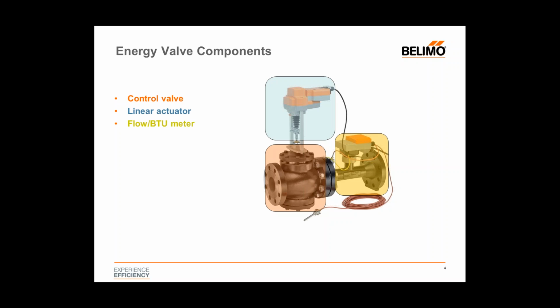The flow meter is now a BTU meter because we add 2 temperature sensors on this assembly. And that's how we understand the delta T and how we conduct our delta T management. One temperature sensor typically goes on the supply side of the coil, and this valve is typically installed on the return side of the coil. By having the difference between the supply and the return water temperature across the coil, we can understand the delta T. And now that we have flow, we have delta T. By using the formula flow times 500 times delta T, we can extrapolate to BTU. So now we not only have a flow meter, but we have a BTU meter as well. That provides us a very robust solution, all assembled in a compact or somewhat compact package compared to if all these components were being installed separately, independently on their own.